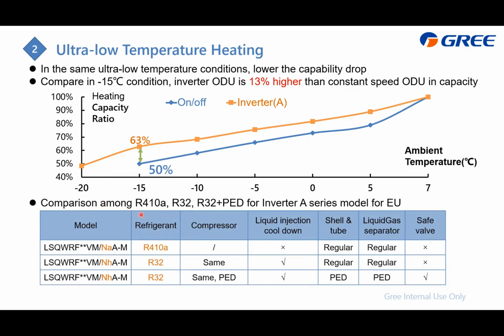This table displays the difference between R410A, R32, and also R32 with PED certificate, the difference for the EU market. Besides the refrigerant being different, the compressor is also a little different. For this PED, we have a special certificate for this compressor, and also for the inside components, including the heat exchanger, gas liquid separator, and there is also a safety valve inside for the PED. And for the R32 series, we have a liquid injection cool down solution, or cycle.